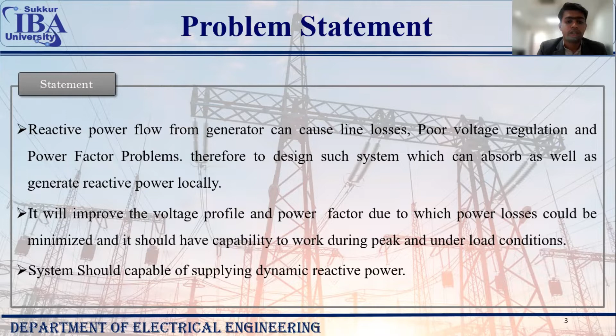Reactive power flow from generator can cause line losses, poor voltage regulation, and power factor problems. Therefore, we need to design a system which can absorb as well as generate reactive power locally. It will improve voltage profile and power factor, due to which power losses could be minimized. It should have the capability to work during peak and underload conditions. The system should be capable of supplying dynamic reactive power.